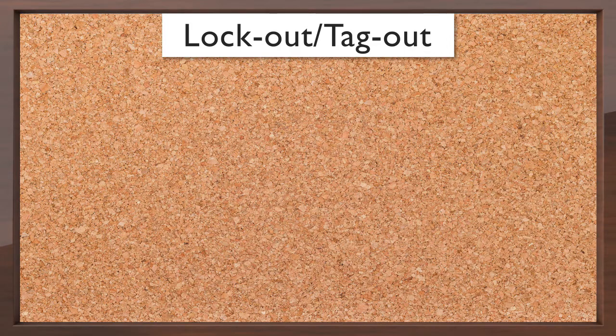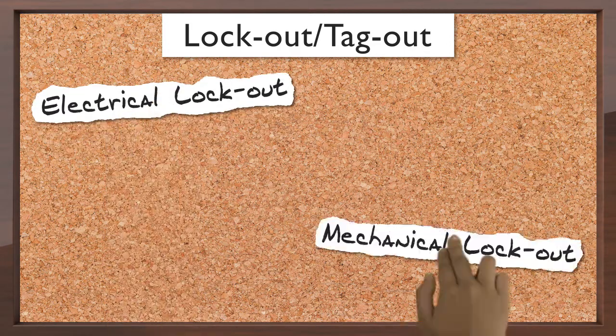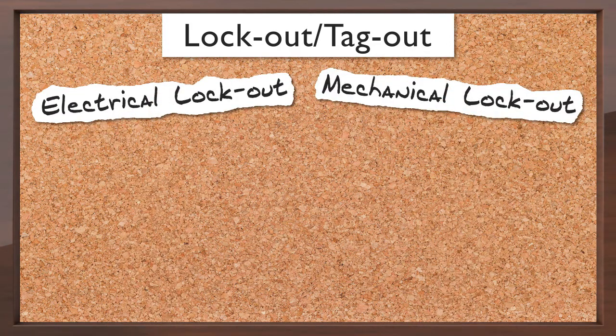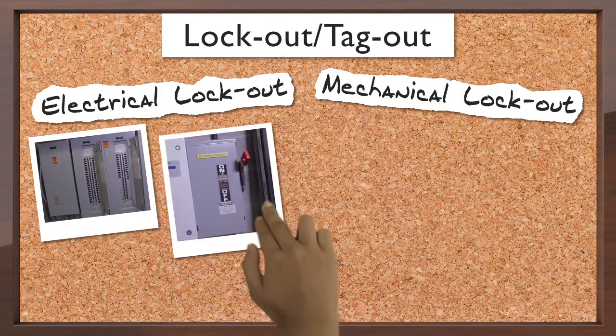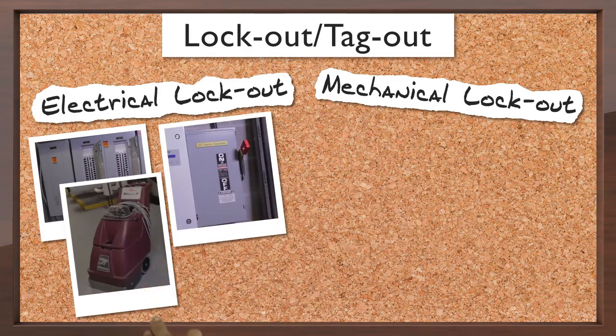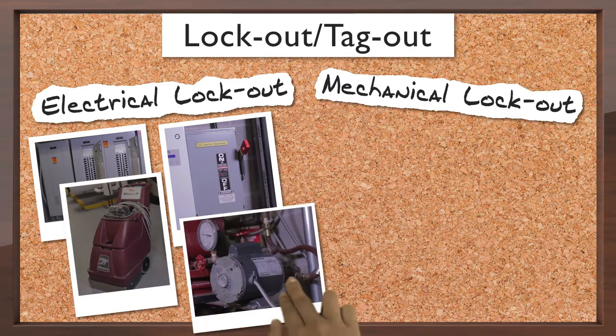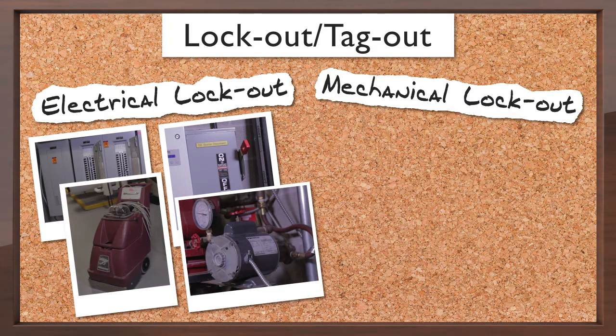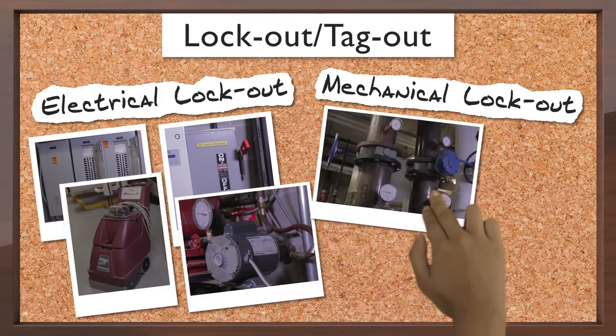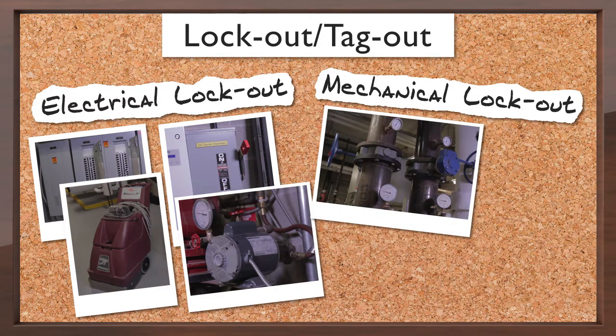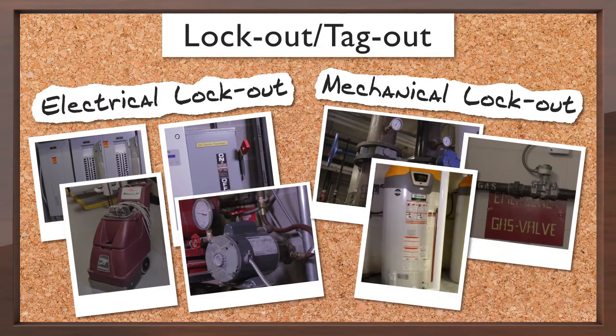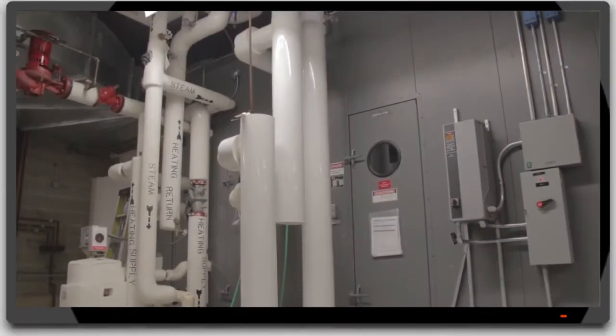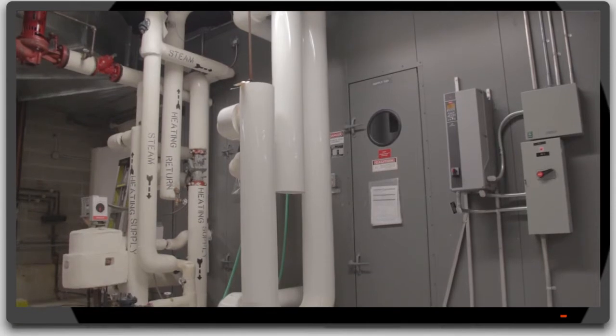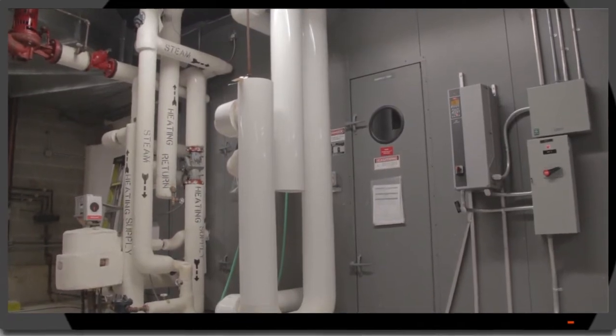There are two types of lockouts: electrical and mechanical. Examples of electrical lockouts include work on circuit breaker panels, main disconnect switches, power cords on equipment, and directly wired equipment. Mechanical lockouts include valve lockouts for pressurized lines, gas, and water. The lockout/tagout demonstration you're about to see is for an air handling unit in a mechanical room that needs to be isolated and serviced.